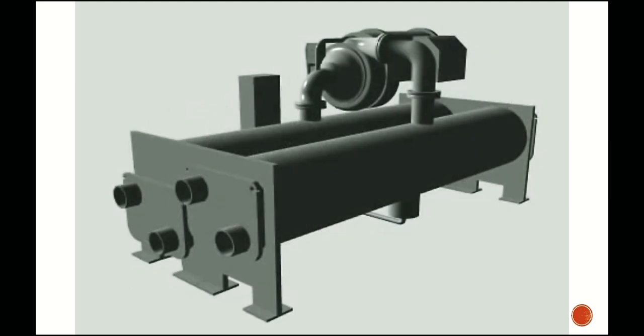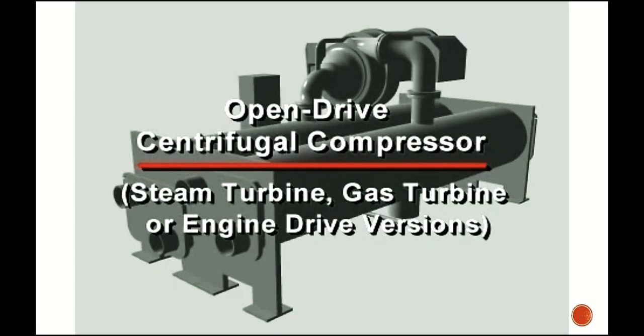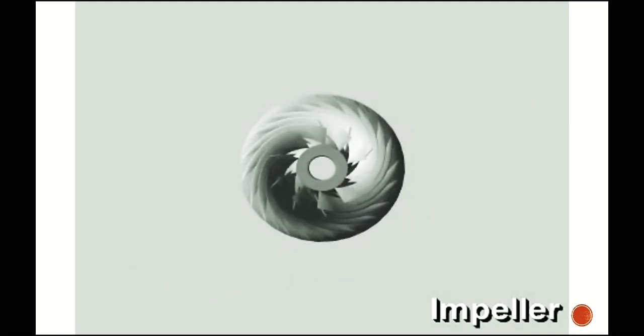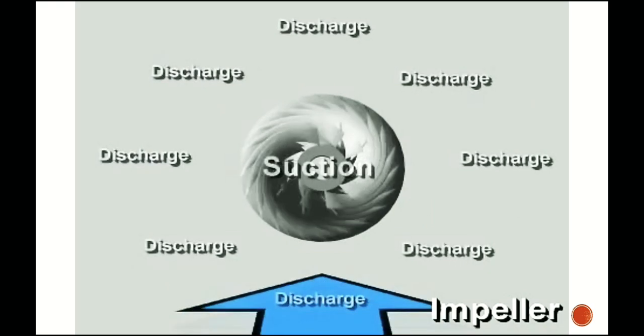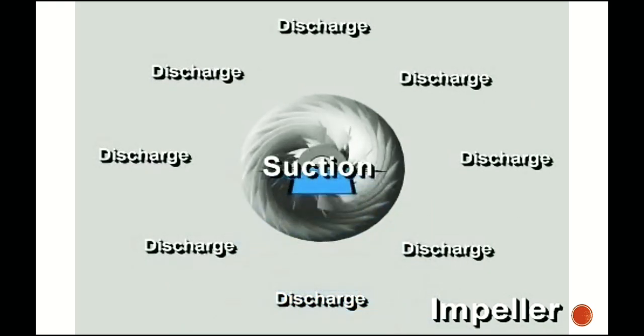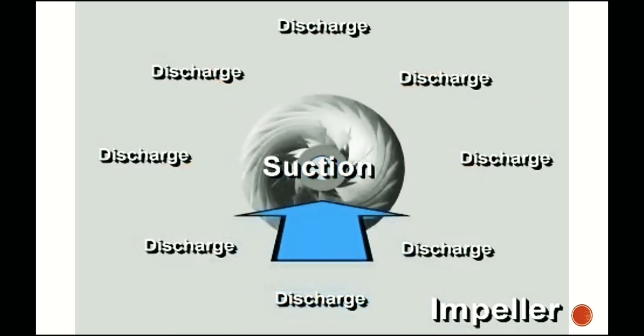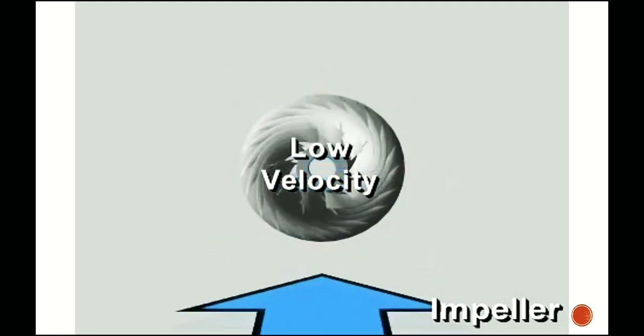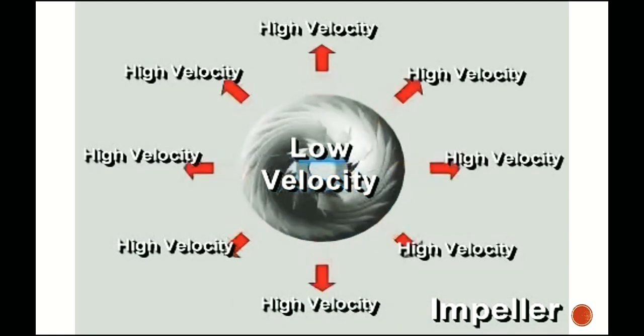Centrifugal compressors are usually driven by hermetic electric motors. However, open-drive centrifugal compressors are also available for applications using steam turbines, gas turbines, or engine drives. The impeller is a rotating circular disc with curved blades driven at high speed by the electric motor. As the impeller rotates, it moves refrigerant vapor from the suction opening at its center to the outer edge using centrifugal force. The vapor enters at relatively low velocity and leaves the outer edge at high velocity.